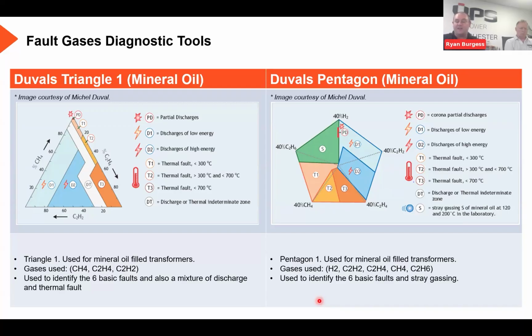This is an indicator of high energy faults such as arcing, which can lead to significant damage. Of those gases that we've just talked about, when they're present it isn't a good thing, but acetylene is the one that's seen as instant: once you see it, you need to take action. But they're all important. It's not just acetylene.